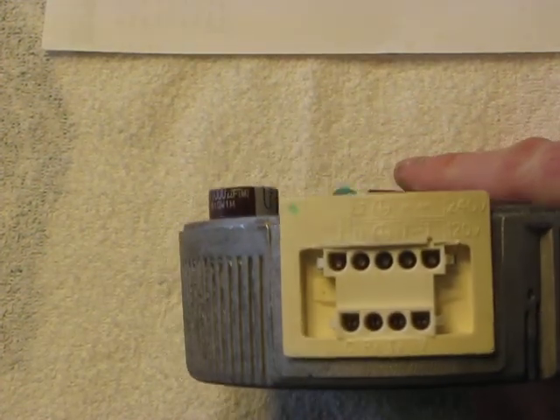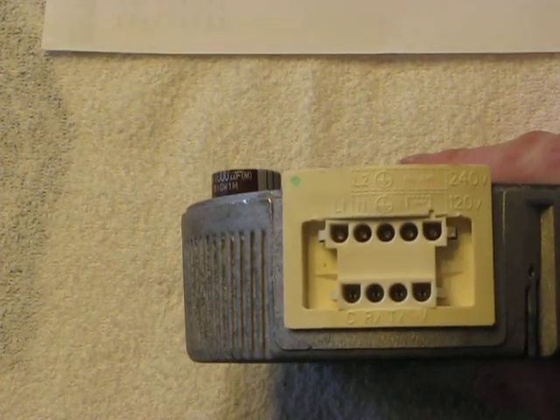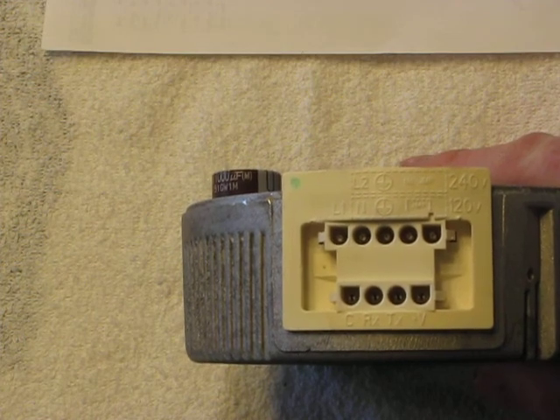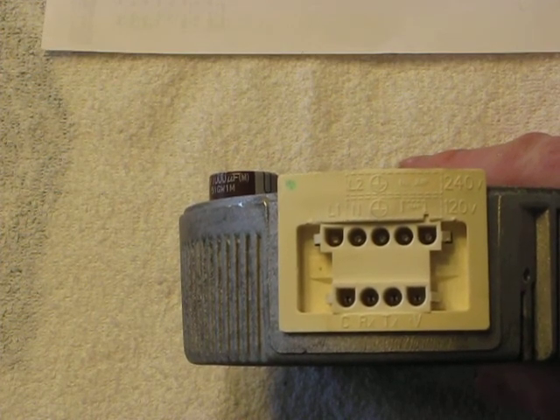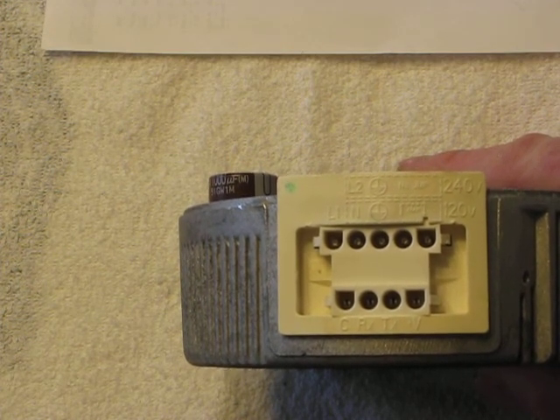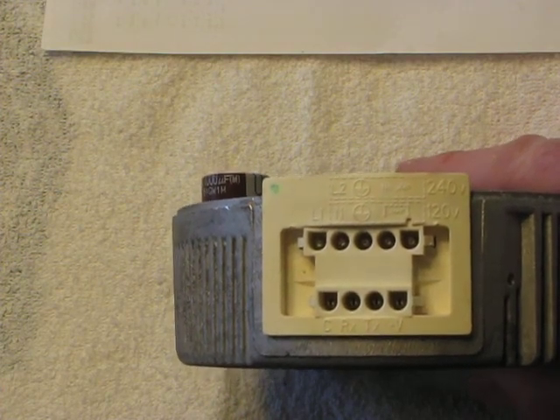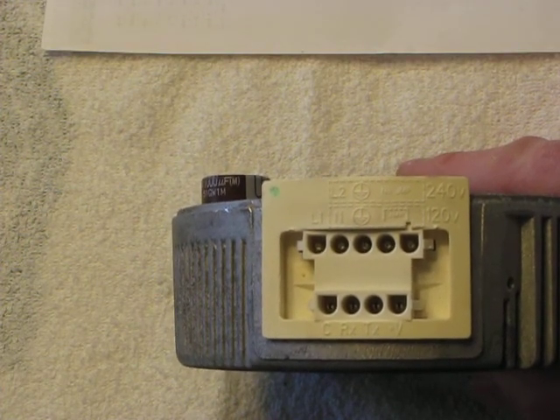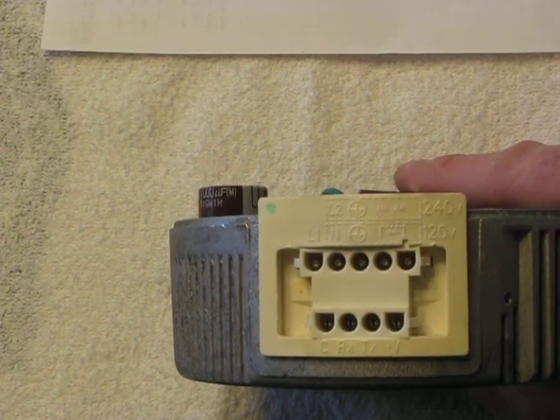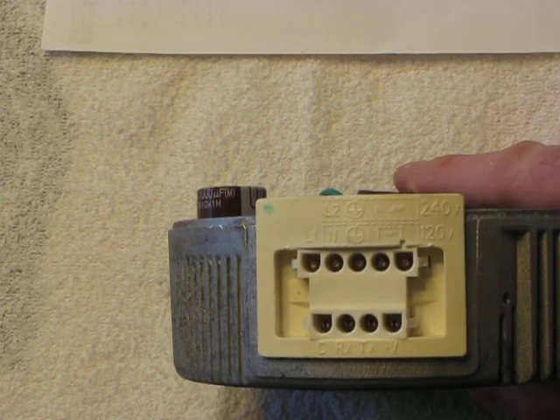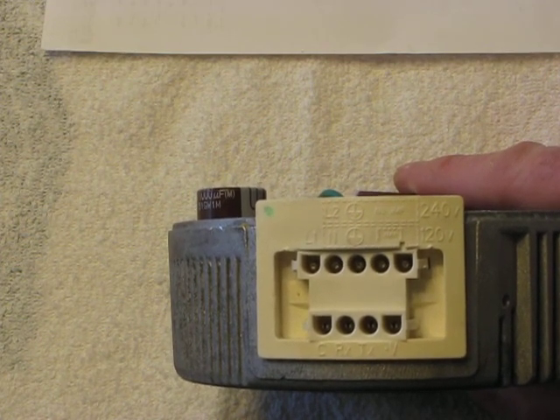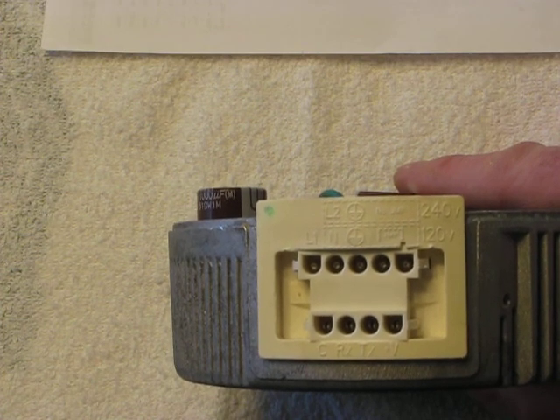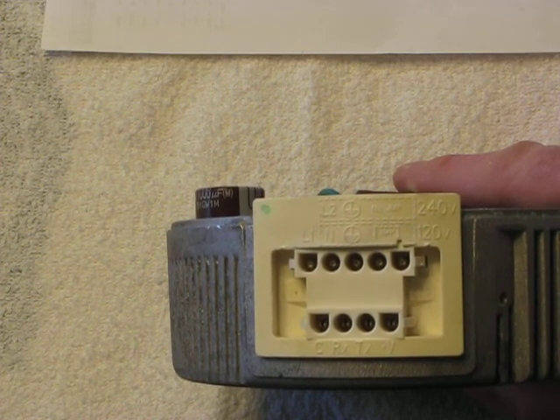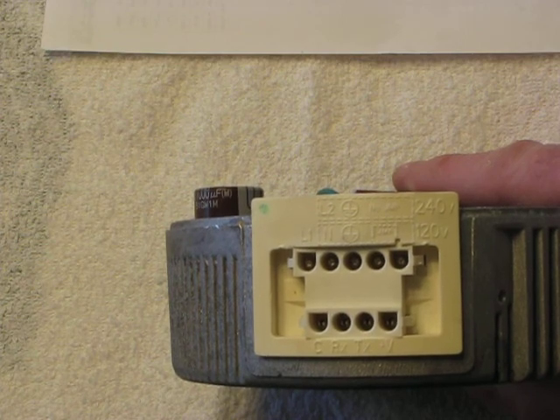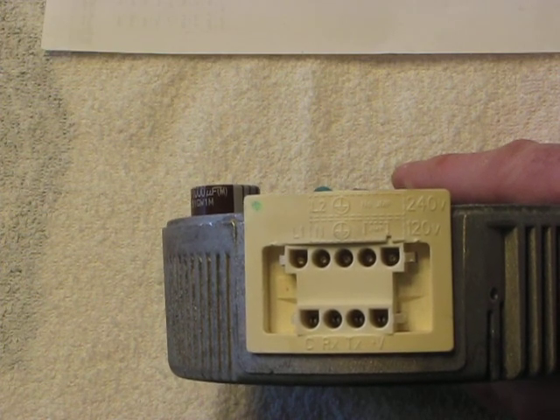Here's the connector. The top connector is the power going in. That's a 5-pin. And on your left would be line 1, neutral, ground, and then the two on the right are a jumper for selecting a 120 volt input from line 1 to neutral. If you leave the jumper off, you put in 240 volts from line 1 to line 2.